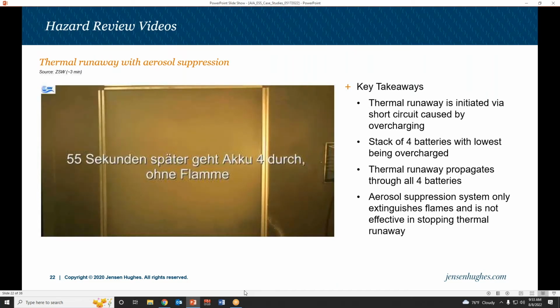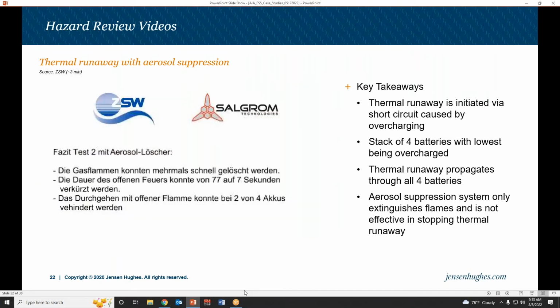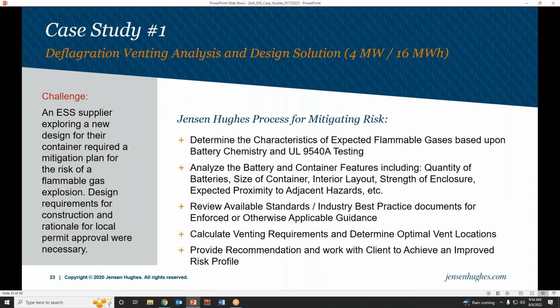Another really important takeaway is: what are we going to do with all that flammable gas now? Imagine this battery system is inside somebody's home, or a building's utility closet, and they thought installing a clean agent or aerosol suppression system would take care of all fire concerns. Yes, no flame—but as the agent decays over time and loses effectiveness, you still have a room full of flammable gas to deal with. That underlines the importance: if somebody puts this in a building, there's got to be an exhaust system. I don't know who wants to be the guy who opens that door.